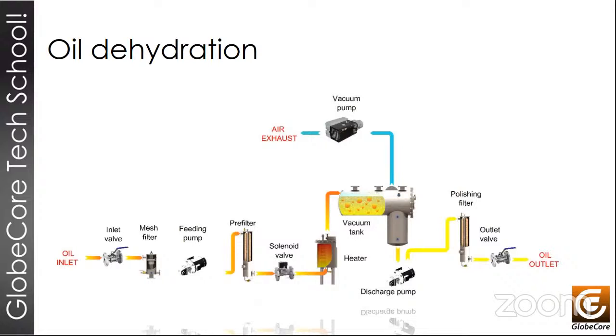So when that is done, the discharge pump activates, and that's usually done with the help of level sensors that monitor the level of oil in the vacuum chamber. And it forces the oil through the next filter, which is the polishing or fine filter with a much smaller micron rating. And then it goes into the outlet, and the outlet may be connected either to the transformer or to an oil container. And this is basically the essence of the dehydration and oil degassing. Next slide, please.